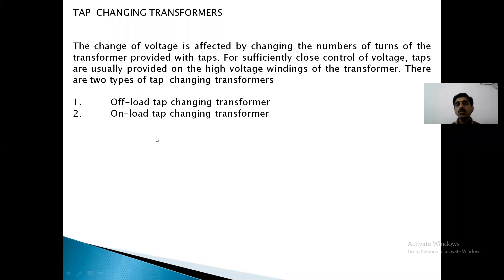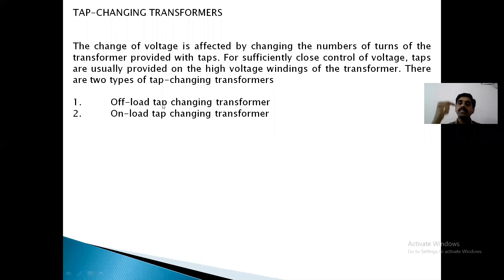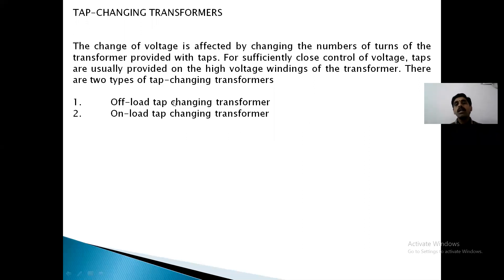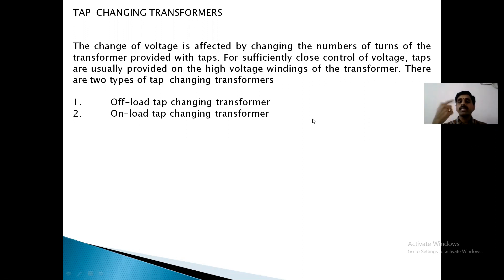There are two types of tap changing transformers: offload and onload. The name itself indicates — offload means you have to disconnect the transformer from the supply, change the tap, then reconnect manually. Onload tap changing transformer means during the supply, when the load is connected, you have to change the tap.